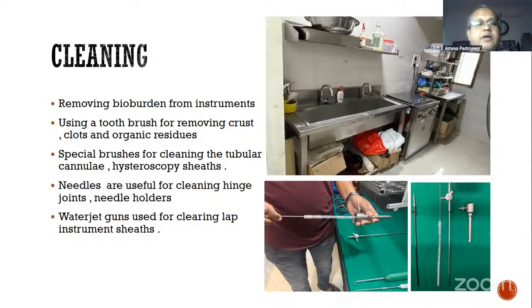Okay. And then the cleaning, especially when it comes to the cleaning of tubular instruments, the cannula. Here you can see me use this long brush to clean the inside of the trocars and the tubular instruments such as the suction cannula or the shafts of any laparoscopy instruments. It is very important to use these brushes. Sometimes you can use air jets or water jets also. We have a small such unit. I will show it in the subsequent picture, which is a small unit which generates compressed air. And this compressed air can be used with a jet to clean the inside of all these tubular instruments.